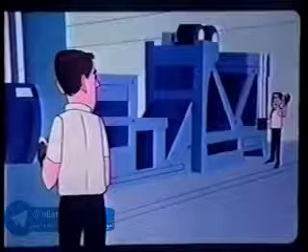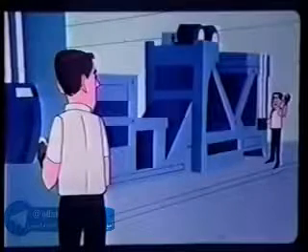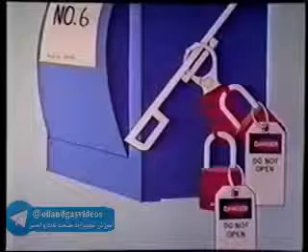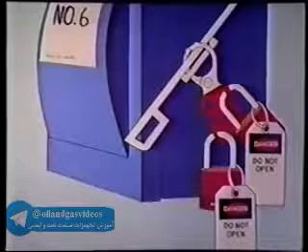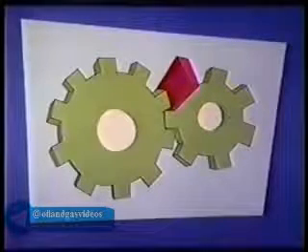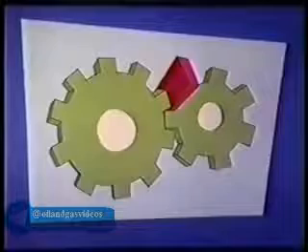To check out the lockout, be sure the proper disconnect has been selected. Recheck the system to be sure the disconnect cannot be switched back on. Try to turn on the machine controls. If the energy is cut off, return the machine or system controls to the off position. Current standards require all electrical equipment to have disconnects. Check the machine or system for any residual or stored energy. Make certain it is rendered harmless, blocked, pinned, chocked, etc. Check for other sources that could present a hazard like suspended parts or chemical reactions.